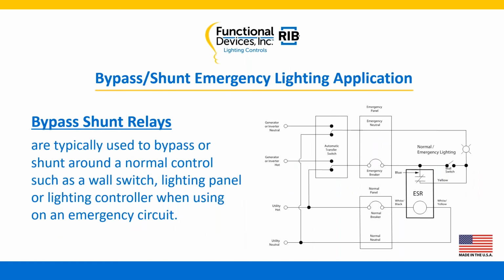First, let's look at our bypass shunt relays. This is just a typical application, but what we've got here is an automatic transfer switch upstream for generator and inverter purposes. We've got our utility power down here below. We've got our ESR sitting out here in the middle to the right. And basically what we're doing with this type of product is bypassing or shunting around a wall switch, a lighting panel, or a lighting controller. And basically what we're doing is moving the power to the normal emergency lighting out there.